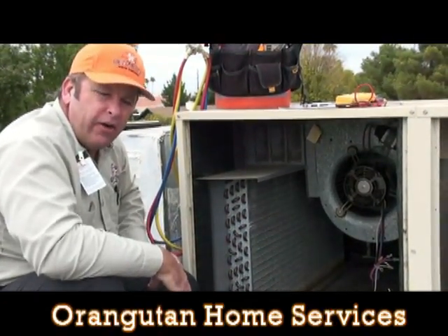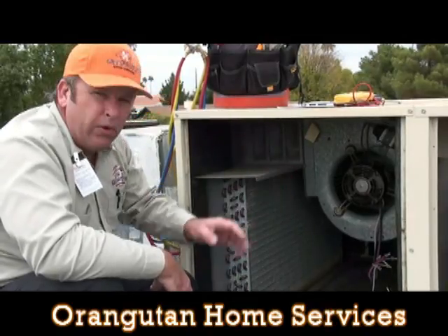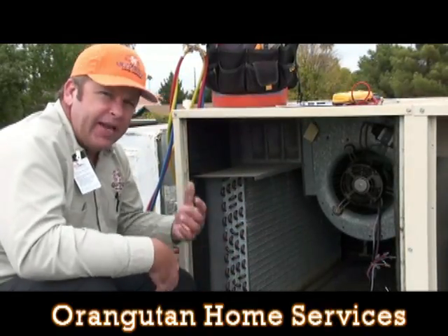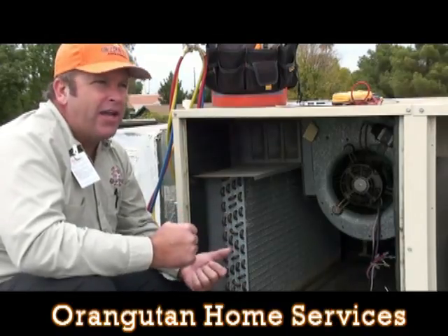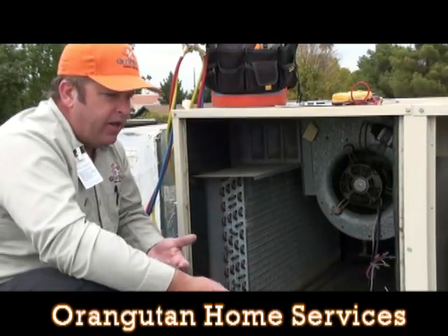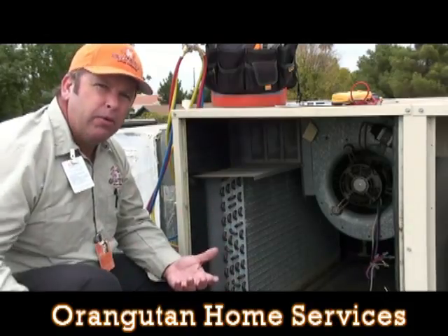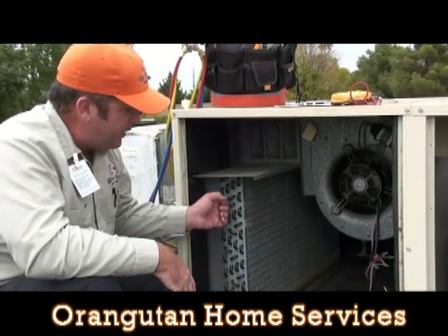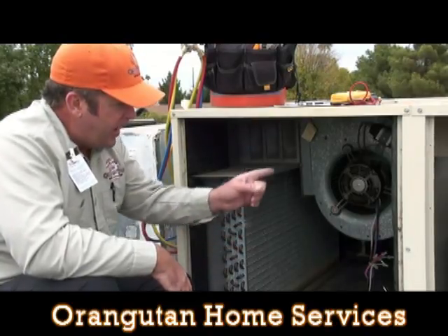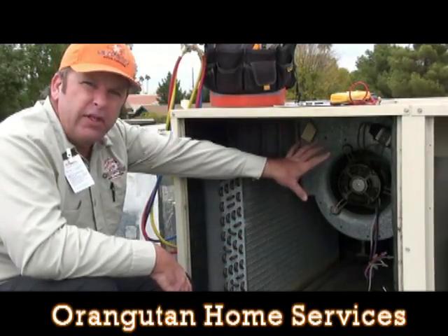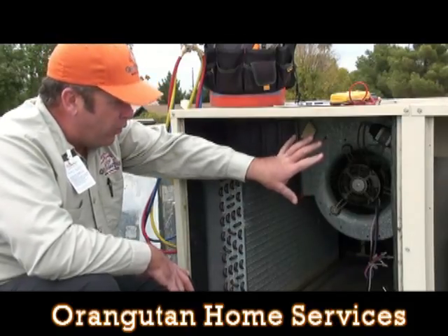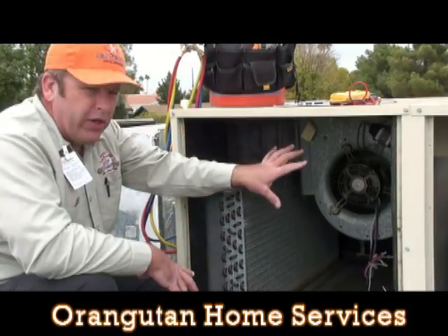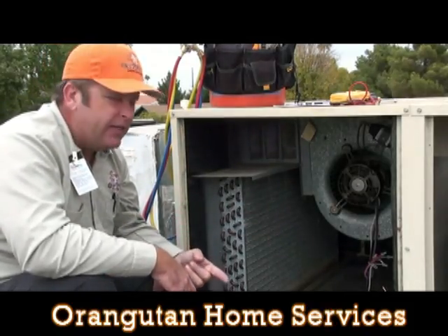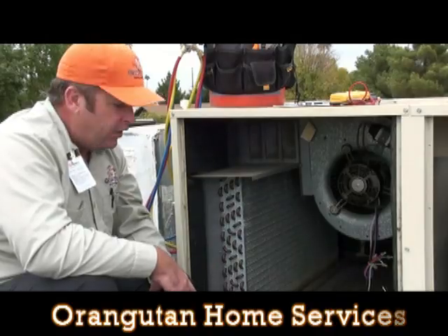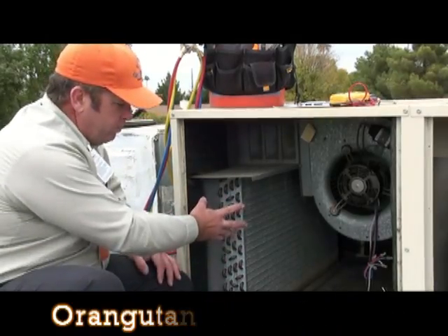So it is important that this coil remain clear and free of any debris in order for this motor to work efficiently. I use the analogy a lot of times with customers: when you take a vacuum cleaner and get caught on a shirt or a towel, you can hear that vacuum cleaner motor ramp up. Well, that's what happens when these coils get plugged up and this motor cannot pull air efficiently across this coil. That motor goes into a vacuum, it overheats, causes fatigue in the windings, and eventually will make the motor fail. So it is important that these coils be kept clean.